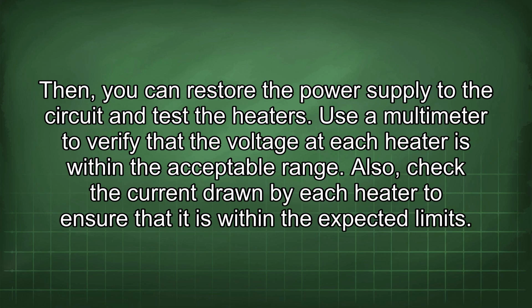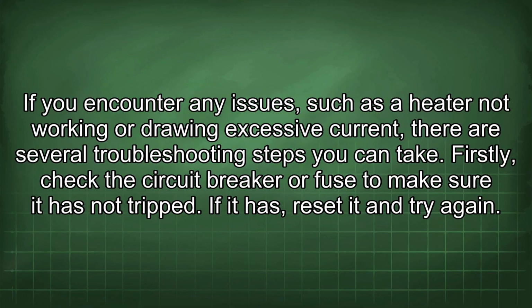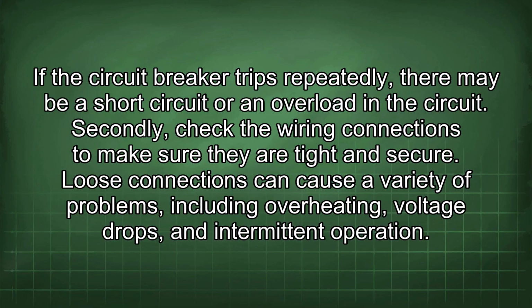Use a multimeter to verify that the voltage at each heater is within the acceptable range. Also, check the current drawn by each heater to ensure that it is within the expected limits. If you encounter any issues, such as a heater not working or drawing excessive current, there are several troubleshooting steps you can take. Firstly, check the circuit breaker or fuse to make sure it has not tripped. If it has, reset it and try again. If the circuit breaker trips repeatedly, there may be a short circuit or an overload in the circuit.